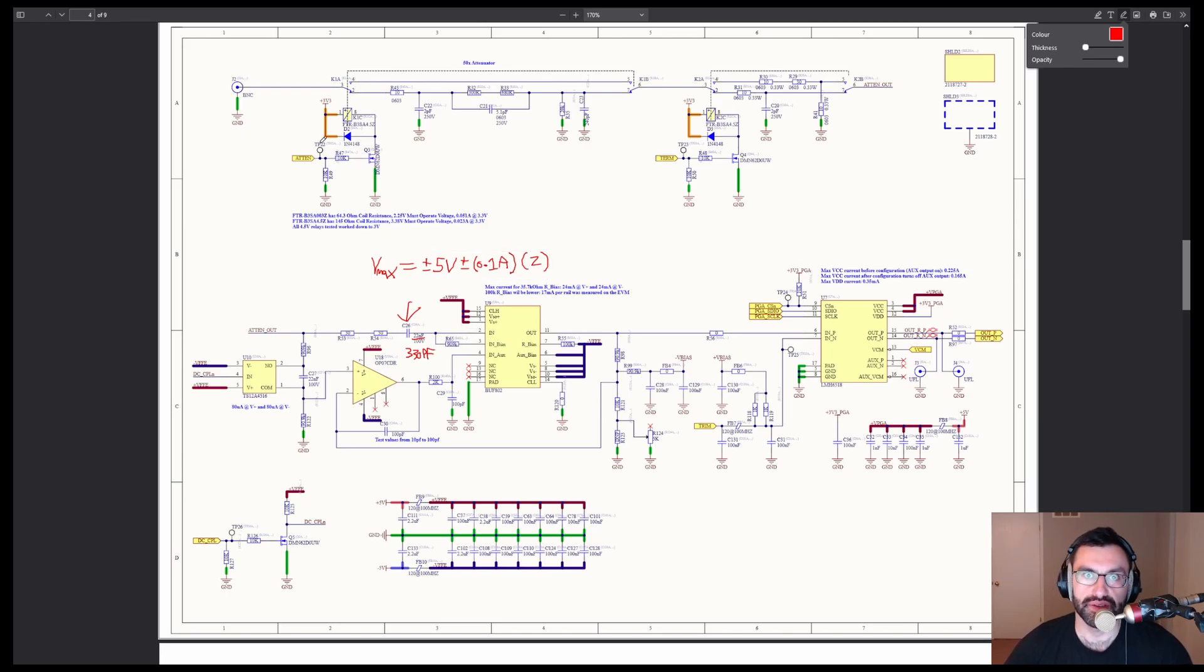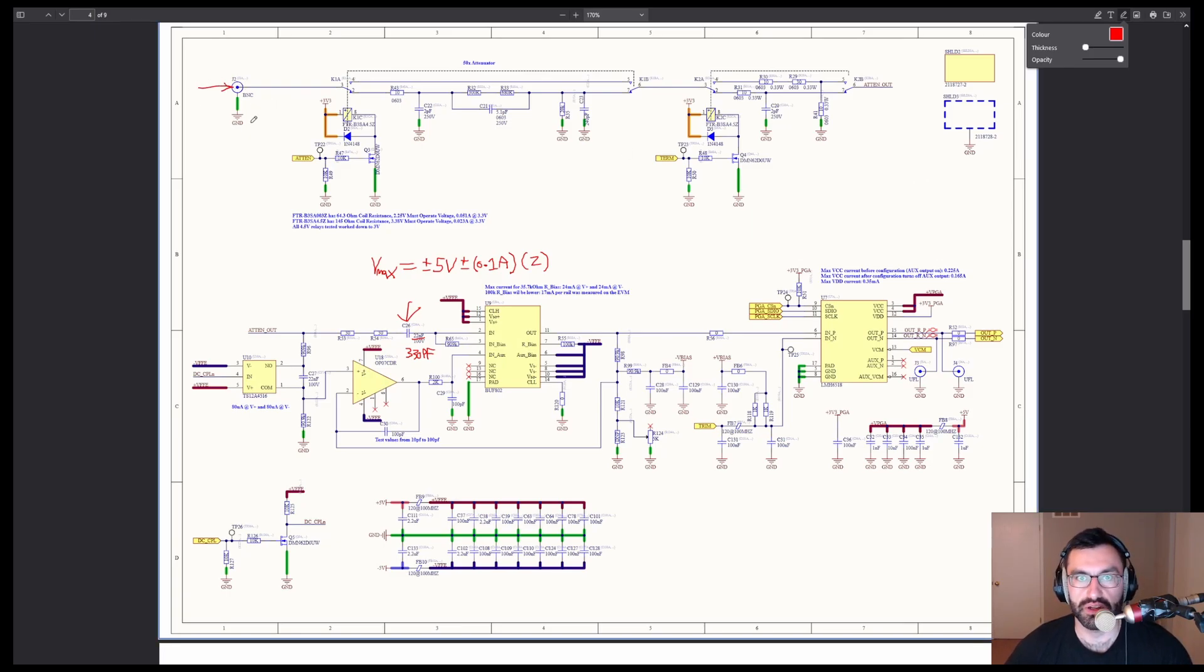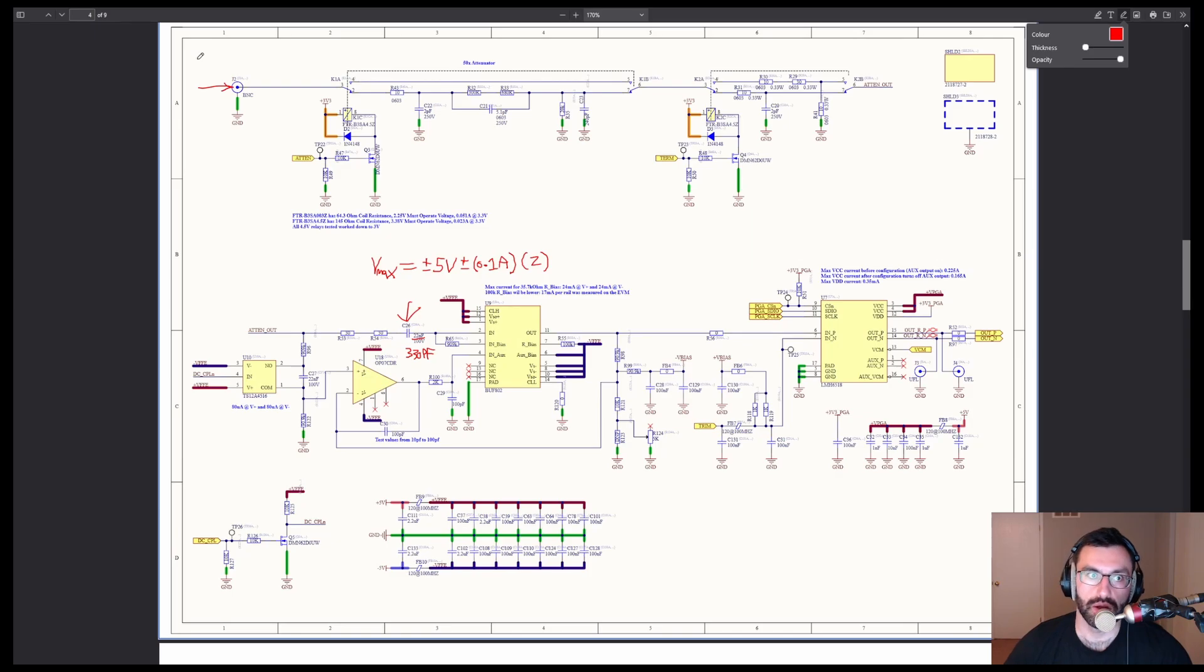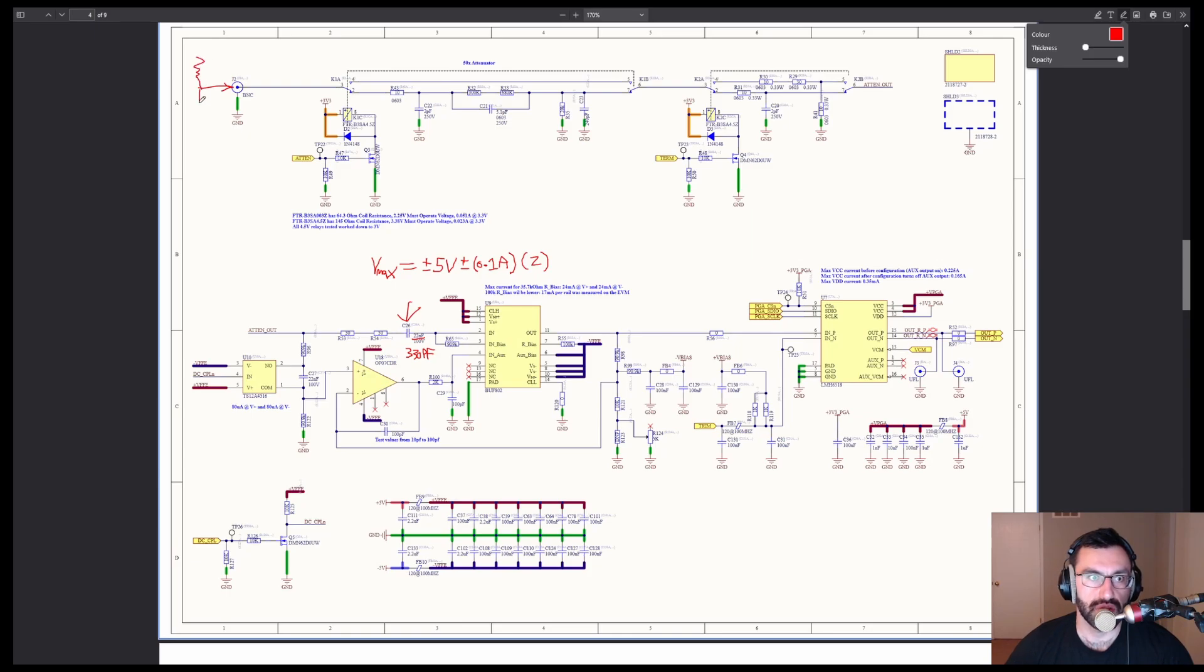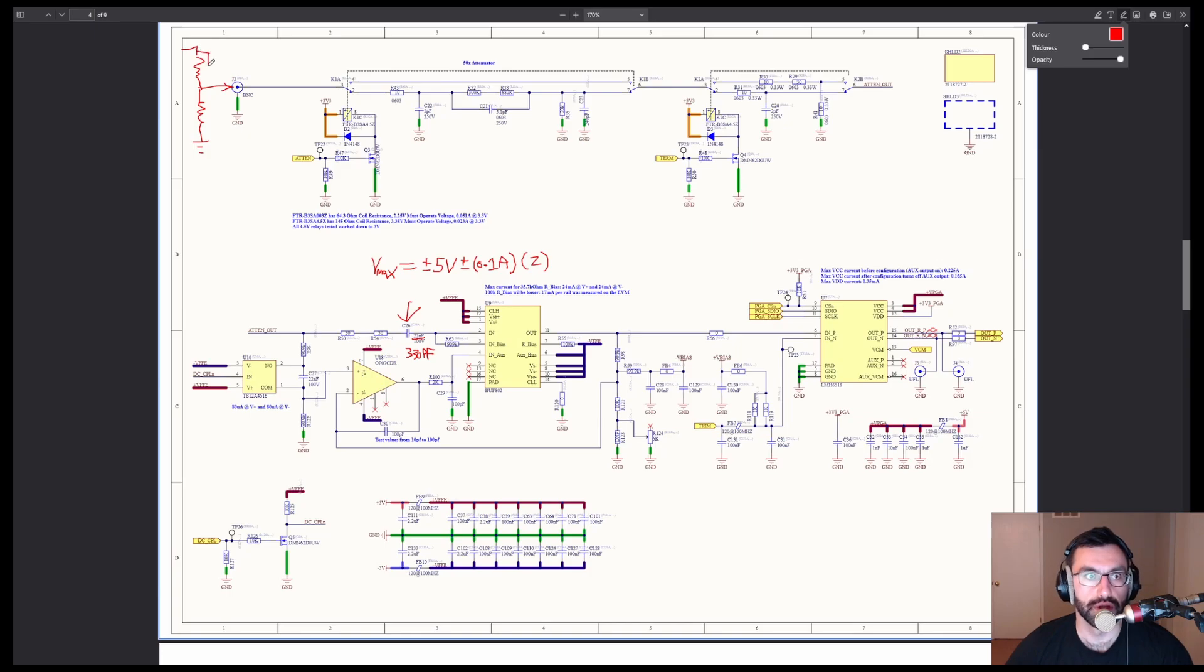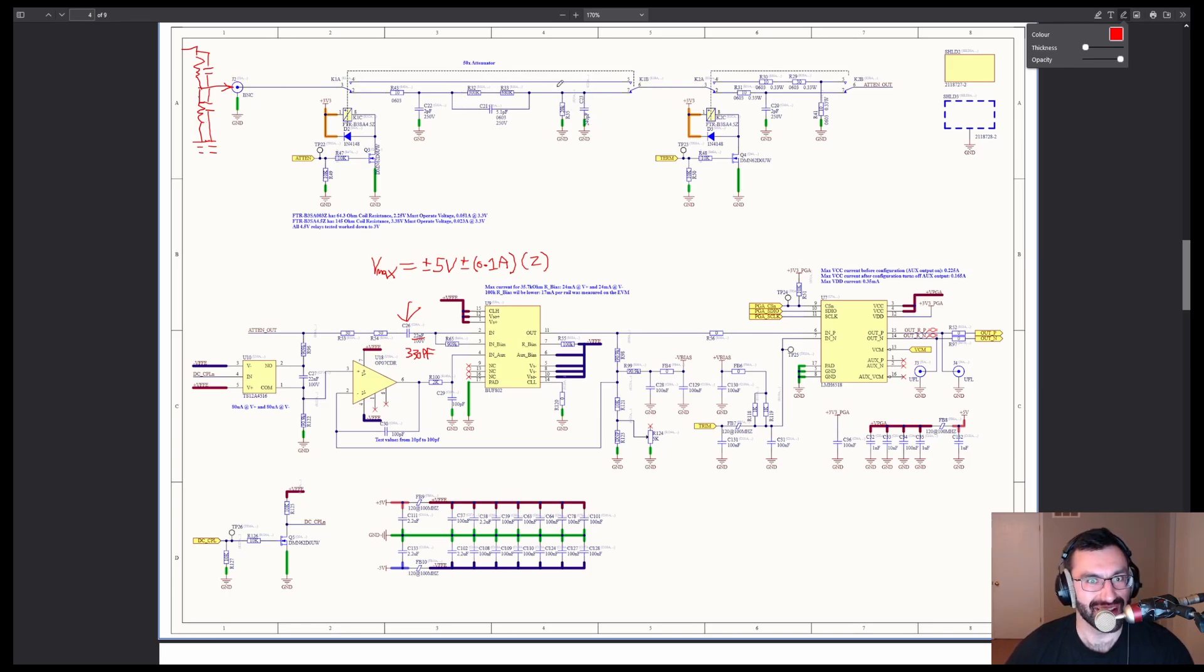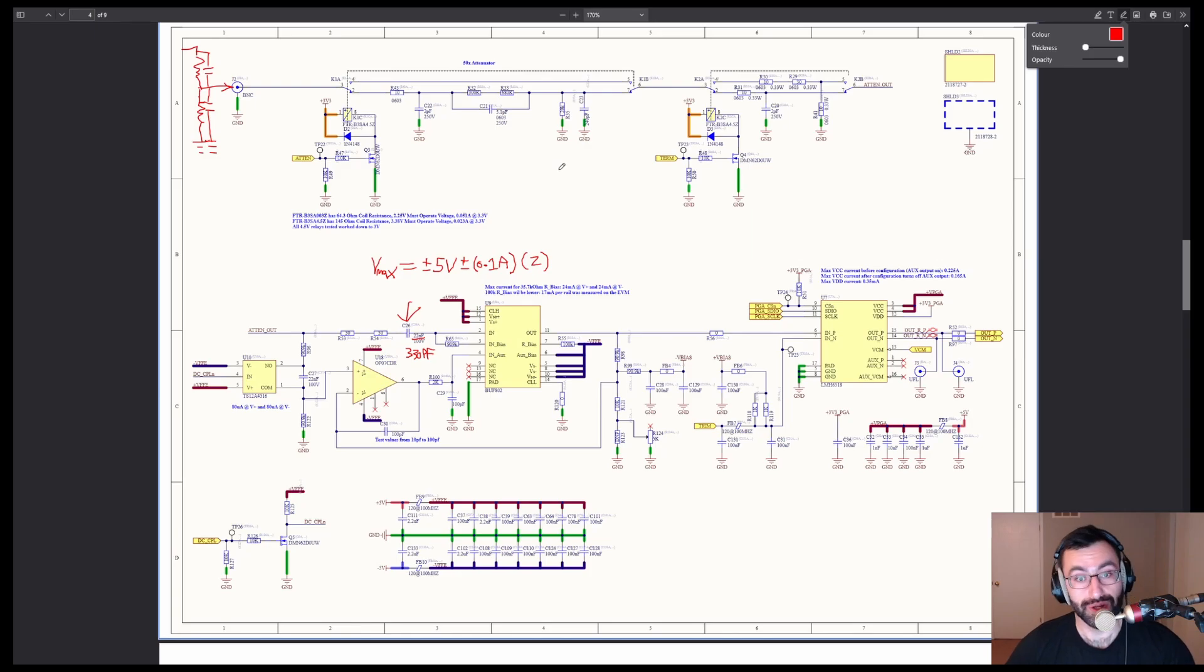The other thing is, these ratings are all for, like, your absolute worst case scenario of a 1x input on 1 megaohm mode, which is already pretty uncommon, because you'd normally be using a 50 ohm input for direct connection like that. But, if you were using, say, a 1x probe, then that's something you can encounter. For use with 10x probes, right, you have another divider there. So, you basically kind of merge the derating curve of the probe with the derating curve of the scope. So, you're going to be safer for longer. And, just to spice things up, I'm going to show you that the probe has more capacitors in it, yay, frequency dependence, and that this also has capacitors in it. So, just a little teaser for another video. I hope you enjoyed this one.